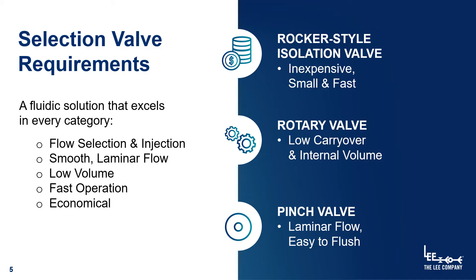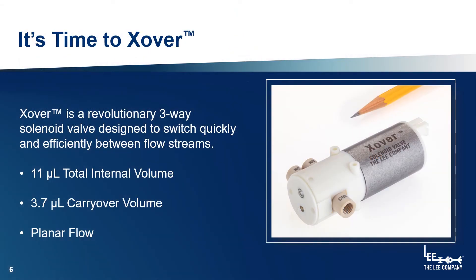Last but not least there is the tried and true external pinch valve, which offers laminar flow through flexible tubing. It is exceedingly easy to flush, although it does carry one critical flaw: the tubing needs to be replaced periodically. In a dialysis instrument tubing replacement is a feature, however in automated diagnostic instruments this maintenance creates headaches for customers. After reviewing the legacy options available, you'll find out quickly that it's time to cross over.